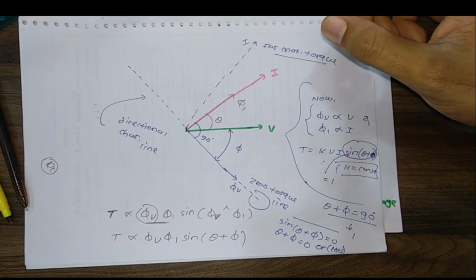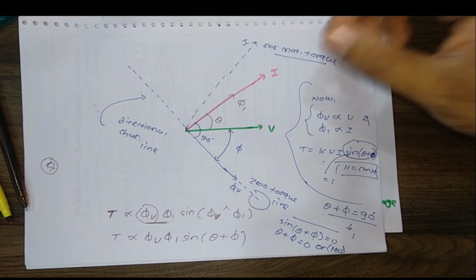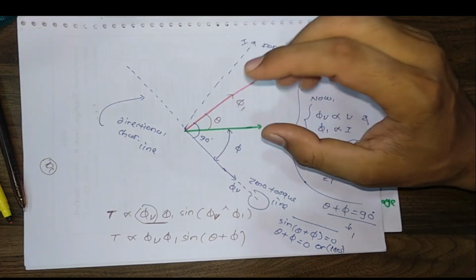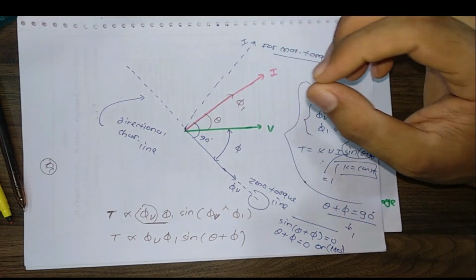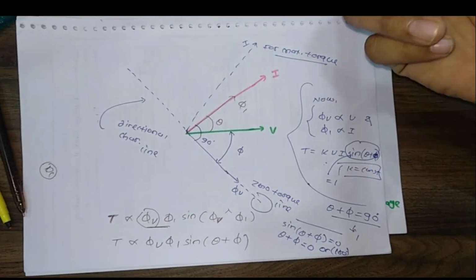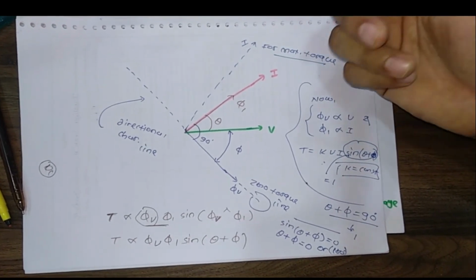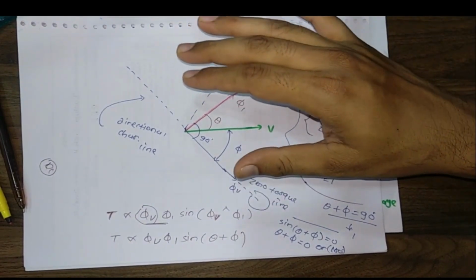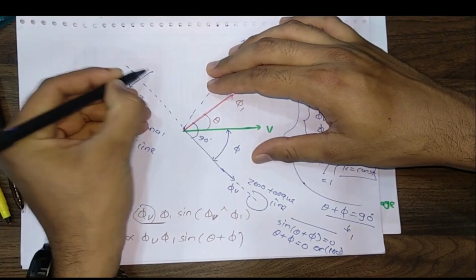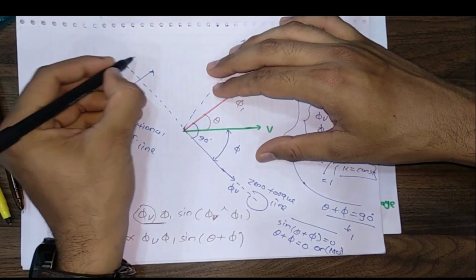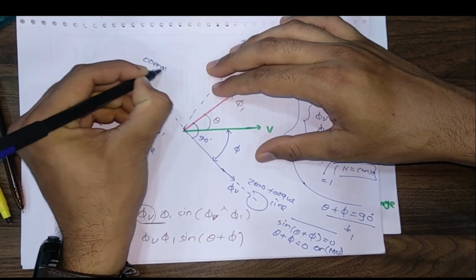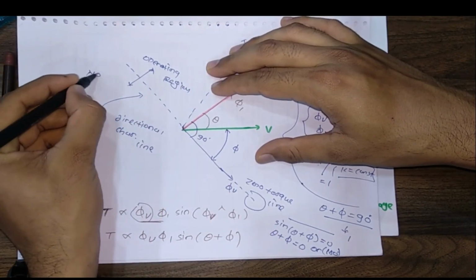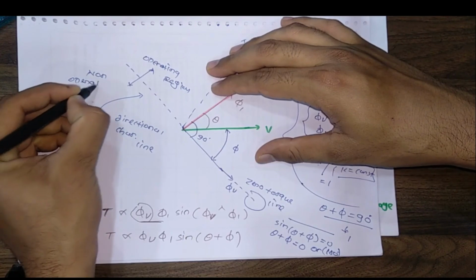Thus the directional element operates provided that the current phasor lies within plus or minus 90 degrees of the maximum torque line. If it is displaced more than 90 degrees, then the element will restrain. Both operating and non-operating regions can be distinguished: this is the operating region, and this is the non-operating region.